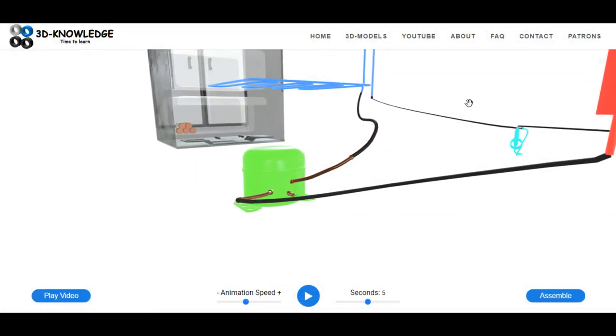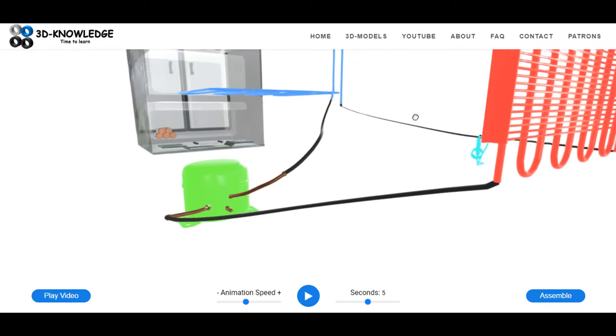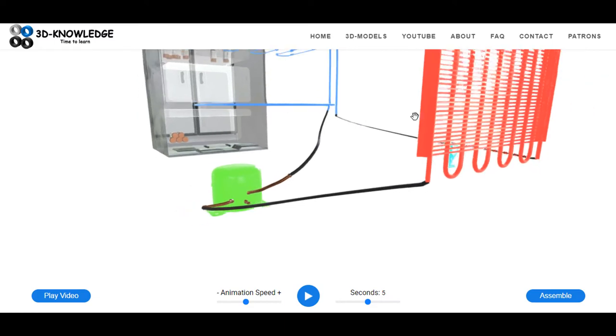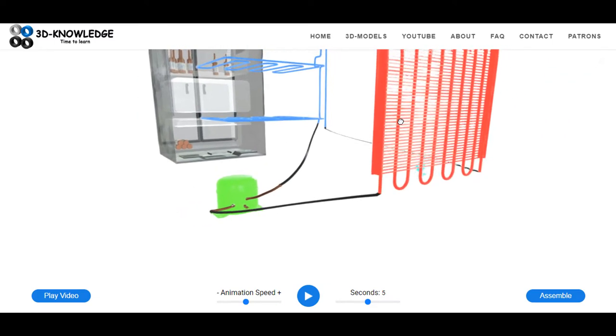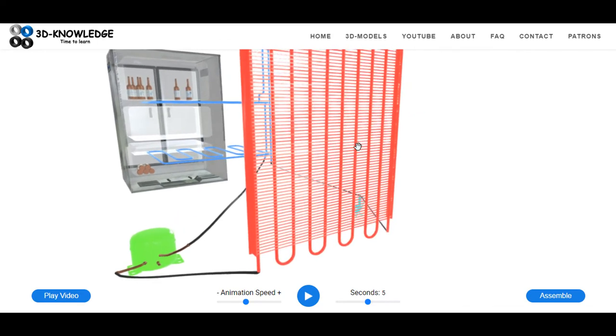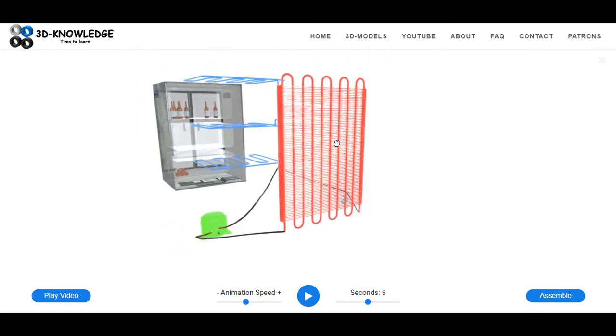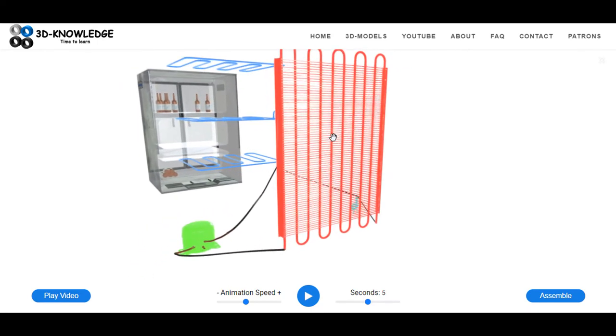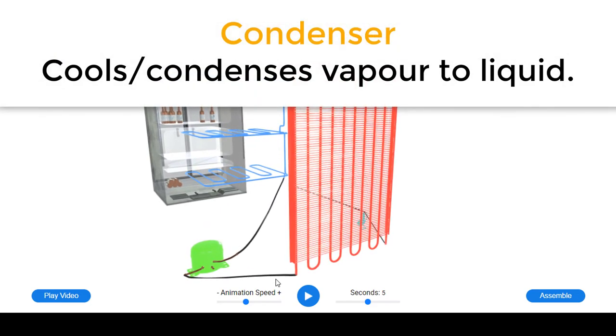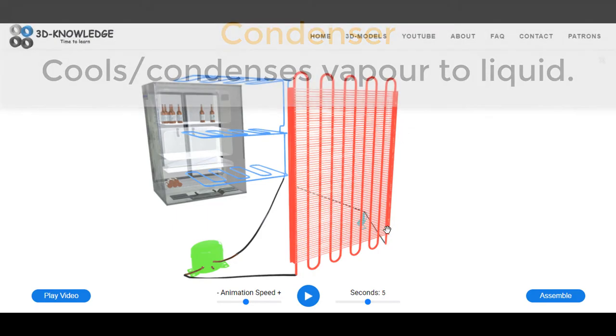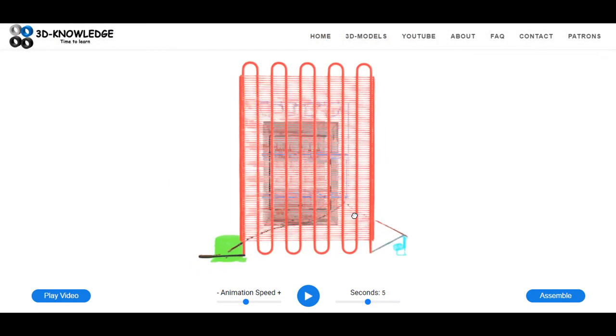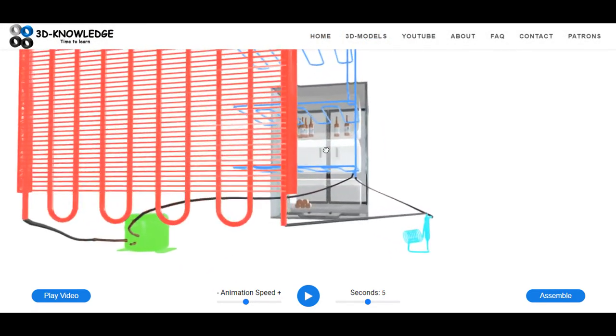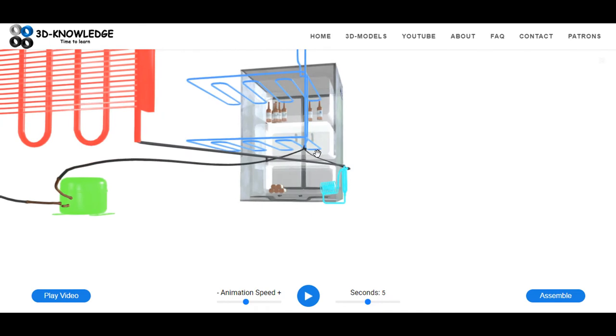So we don't really want to use this hot vapor. So what we're going to do is send it to a heat exchanger, what they call a condenser. Now the condenser will cool the gas down. It does this by passing it through tubes and these tubes radiate the heat to ambient air. So the air will get warmer and the refrigerant inside the tubes will become cooler. Now at this stage we have a high pressure liquid, and this high pressure liquid is then discharged to a capillary or an expansion device.